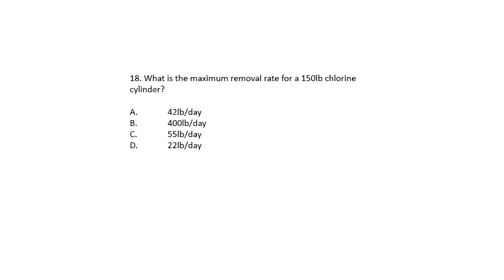Question 18. What is the maximum removal rate for a 150-pound chlorine cylinder? 42 pounds a day, 400 pounds a day, 55 pounds a day, or 22 pounds per day? The maximum removal rate for a 150-pound chlorine cylinder is 42 pounds per day. Anything over that will cause the line to freeze.